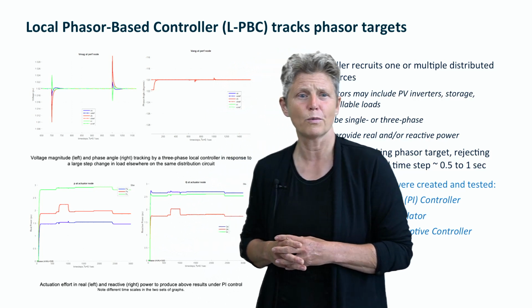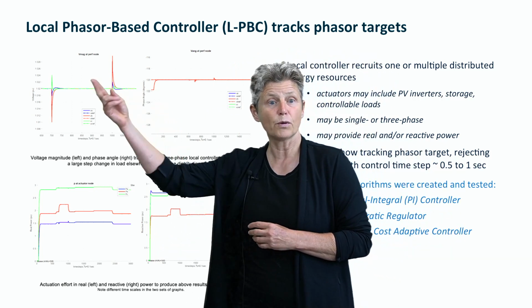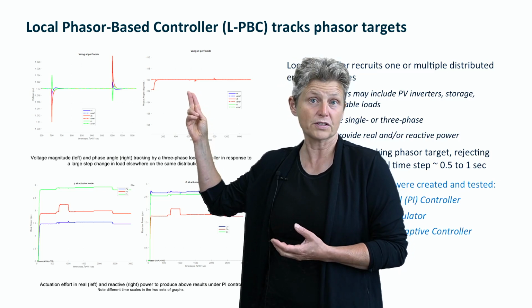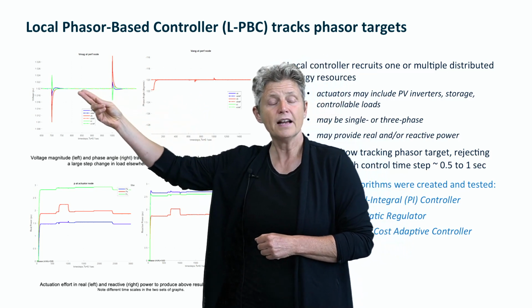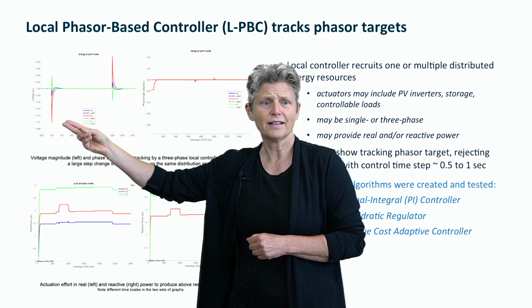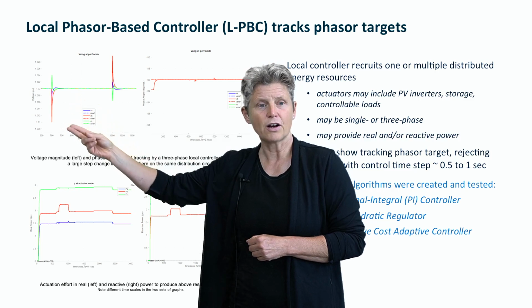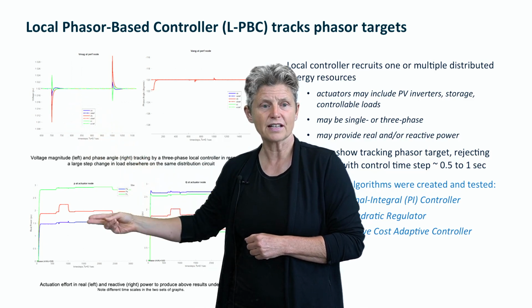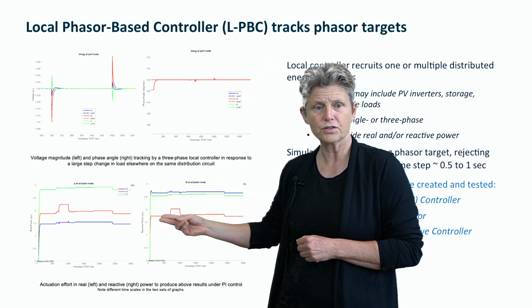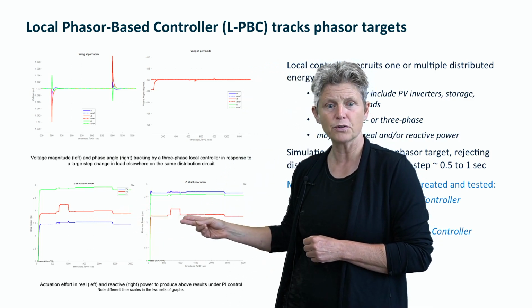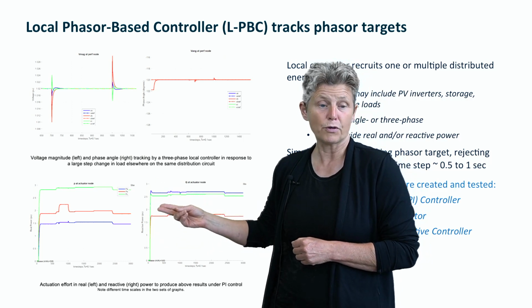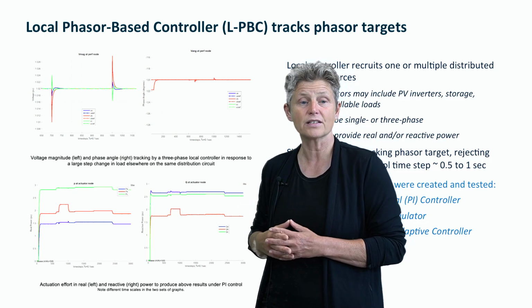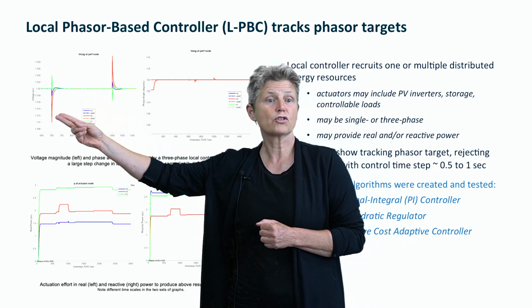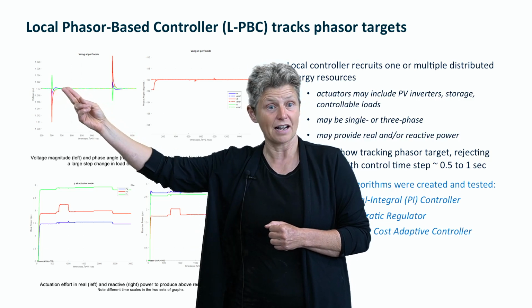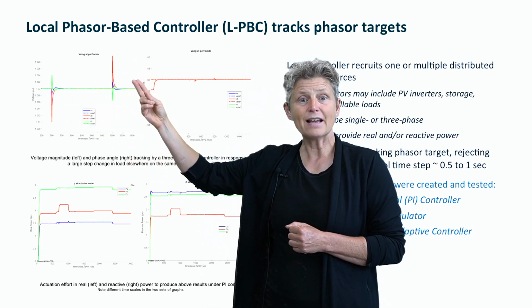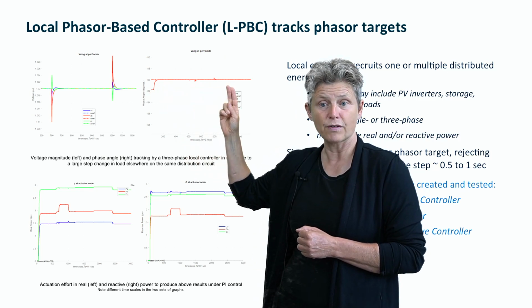Here we're looking at voltage magnitude and angle at the performance node, in this case node 632. We've simulated some really big disturbances. The 3 colors are the 3 phases. With actuation from the resources, both real power P and reactive power Q, in per unit (which would be many kilowatts), we're restoring the voltage magnitude to its desired value and restoring the voltage phase angle to its desired value.